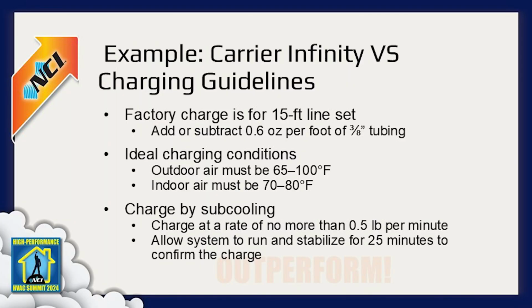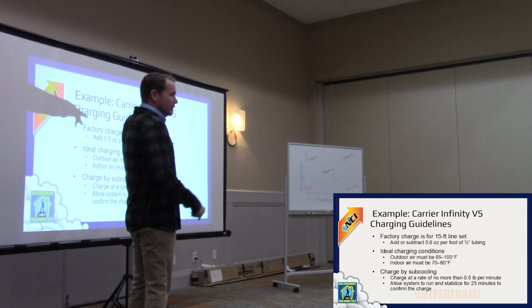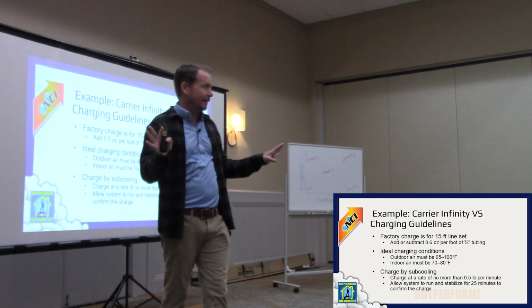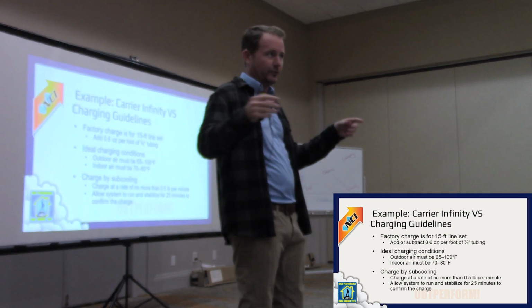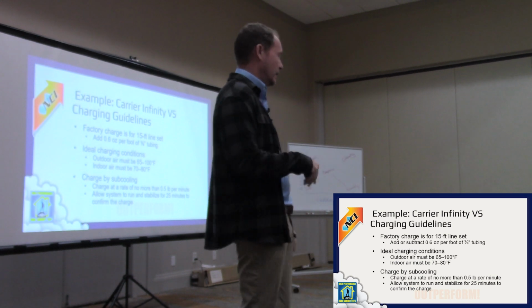Example, Carrier Infinity VS is charged for a 15-foot line set. You add 0.6 ounces per foot of 3/8 tubing. That's universal. The amount you add based on tubing size isn't a manufacturer thing, it's just universal depending on how much refrigerant can be held by that copper.